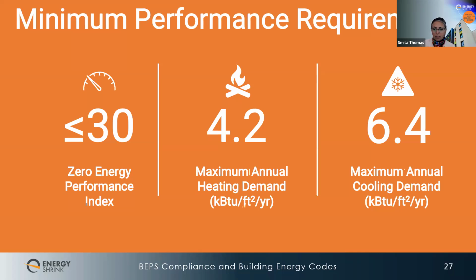Under Appendix Z, the design must demonstrate maximum annual heating and cooling demands. This ties back to passive measures - if you have a really efficient building envelope, a good building skin, you'll have reduced heating and cooling demands, and that's what DC is looking for, because lower demands mean you use less energy to meet them.